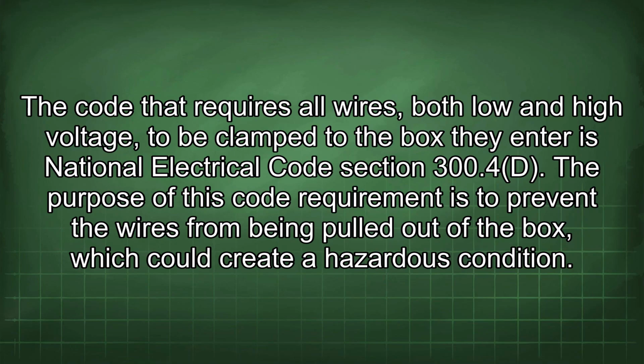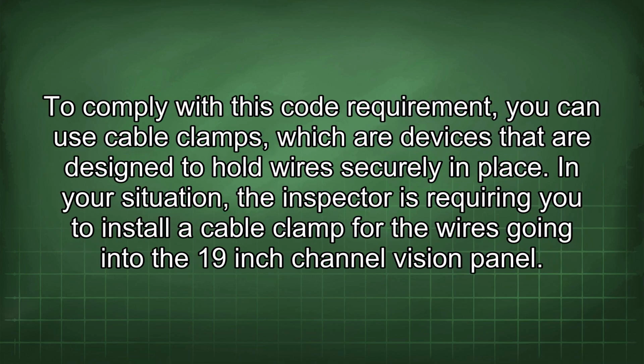The code that requires all wires, both low and high voltage, to be clamped to the box they enter is National Electrical Code Section 300.4D. The purpose of this code requirement is to prevent the wires from being pulled out of the box, which could create a hazardous condition. To comply with this code requirement, you can use cable clamps, which are devices that are designed to hold wires securely in place. In your situation, the inspector is requiring you to install a cable clamp for the wires going into the 19-inch channel vision panel.